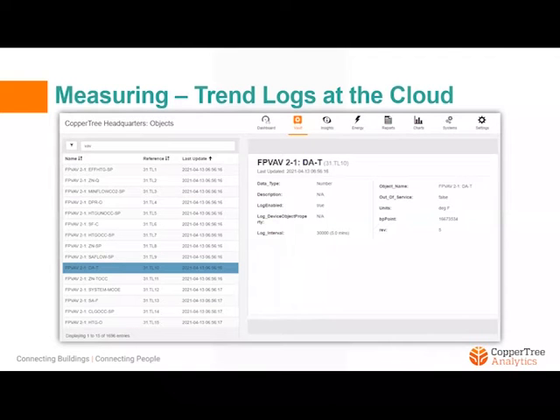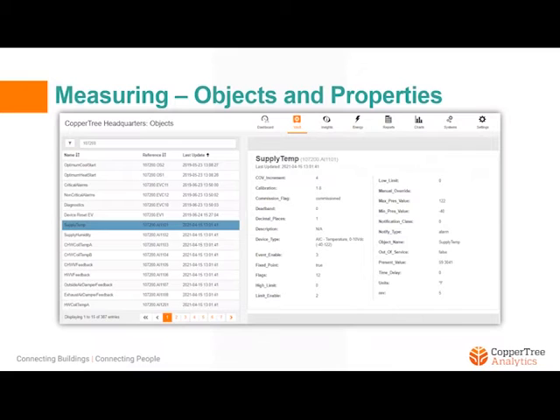Trend logs at the cloud, on the other hand, are not created in the BAS controllers. Rather, edge devices capture data points and their values from BAS controllers and create trend logs at the cloud, where they can then be visualized and processed by analytic engines. The BAS points or objects, along with their various properties and values, can also be captured by edge devices and shipped to the cloud. Our analytics platform Kaizen then becomes a historical database for each system point. Some valuable properties can include point value, units, out of service, calibration, and commission and decommission flags.